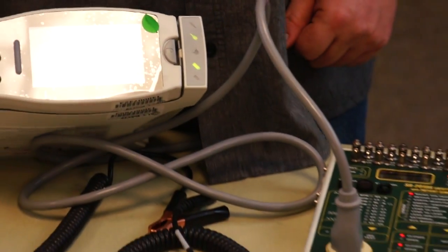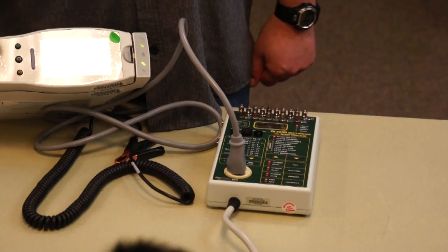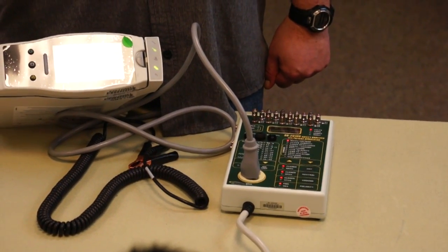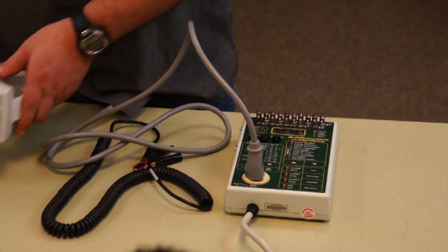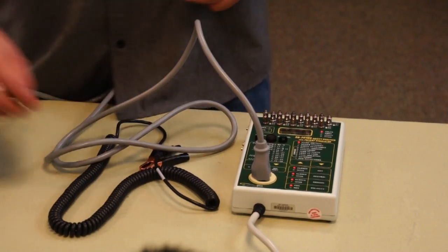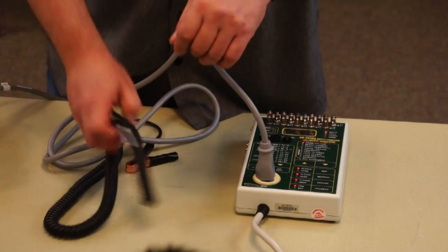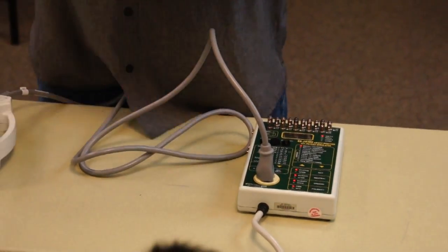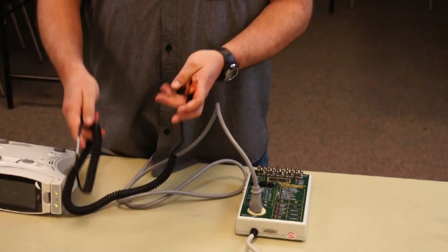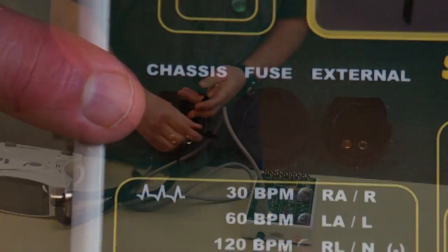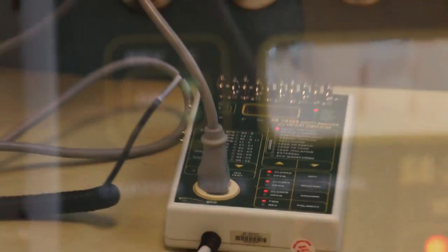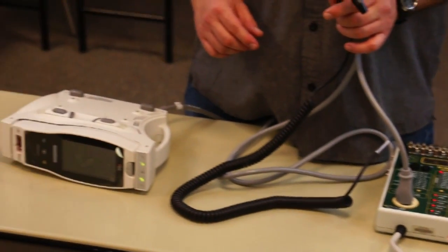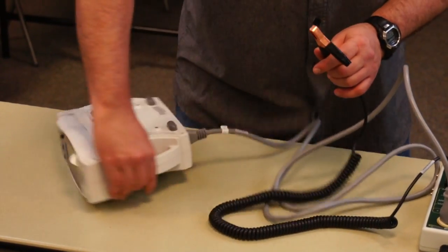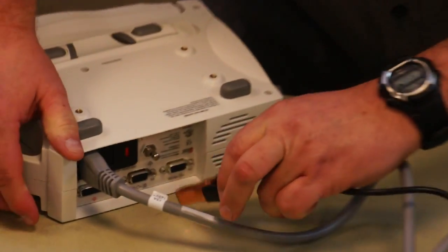The first test that we will perform is the ground wire resistance test. In order to do this, we will need to have a Kelvin cable connected to the chassis input on the analyzer and connect the other end to the ground lug on the device under test.